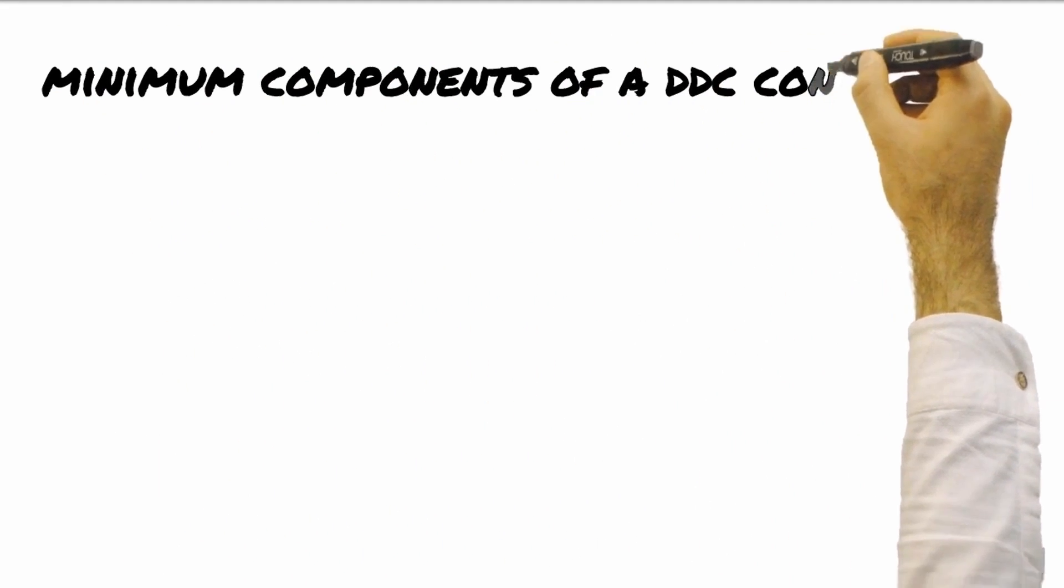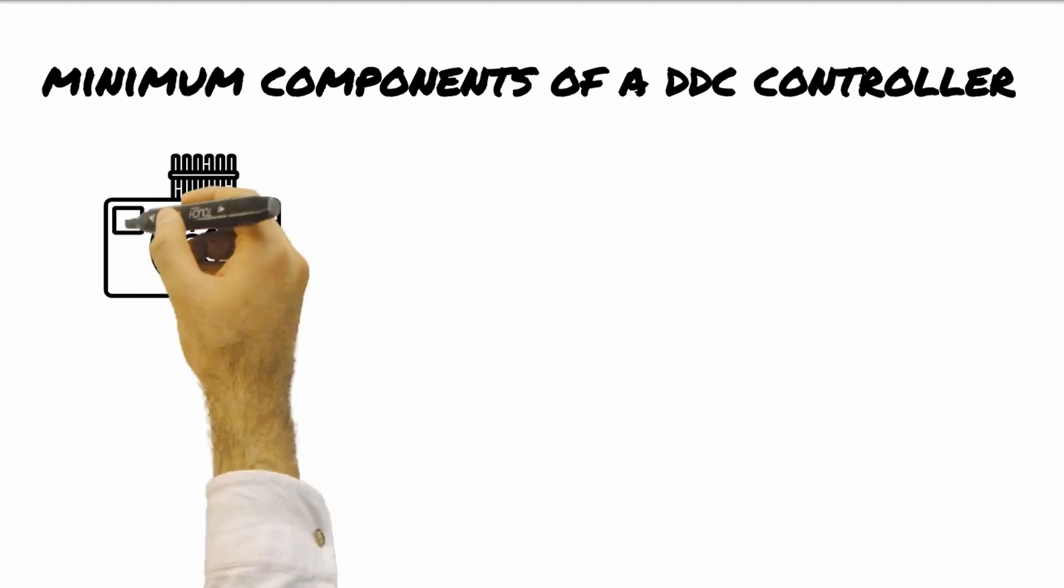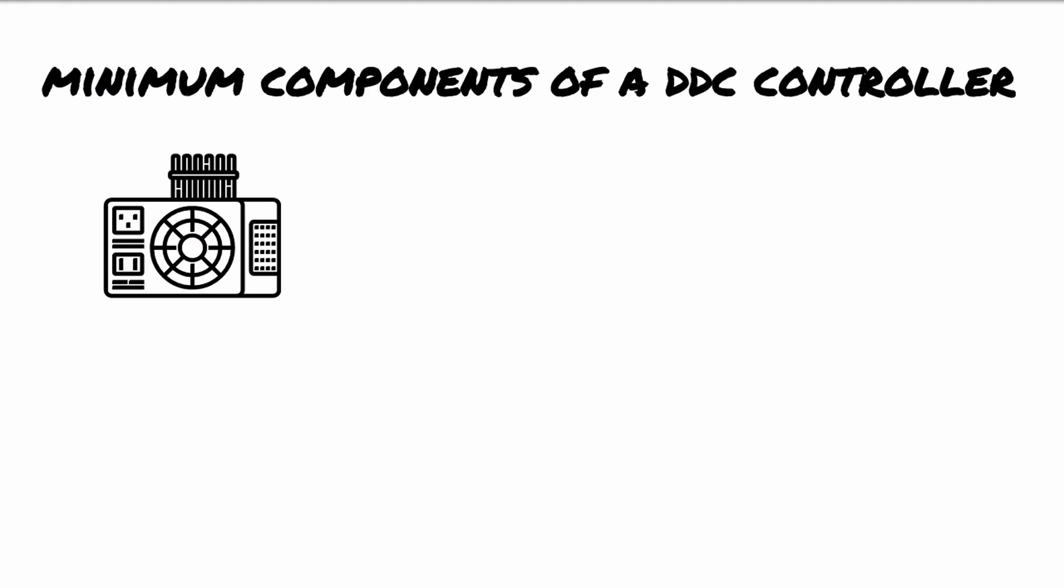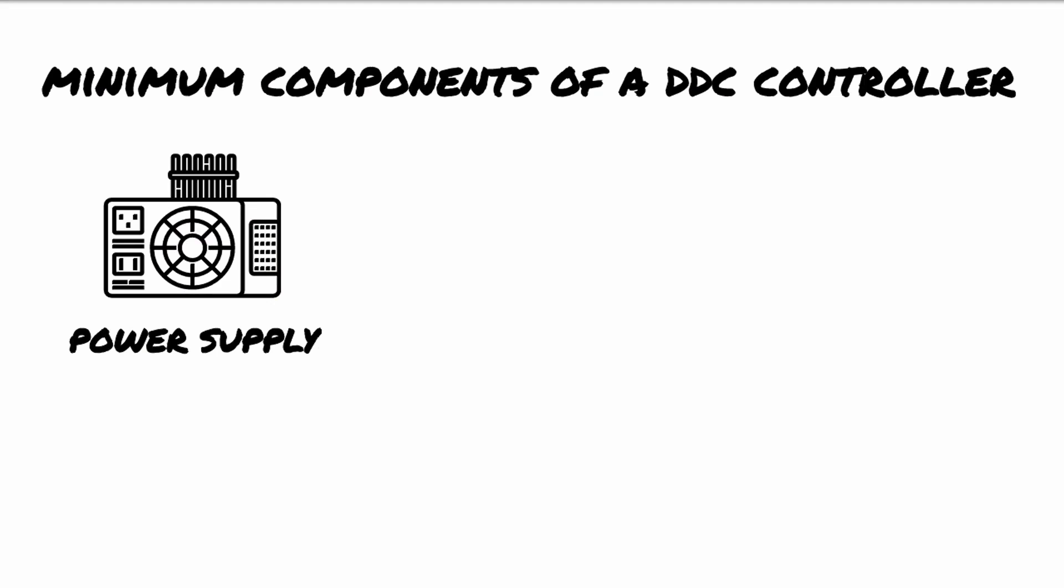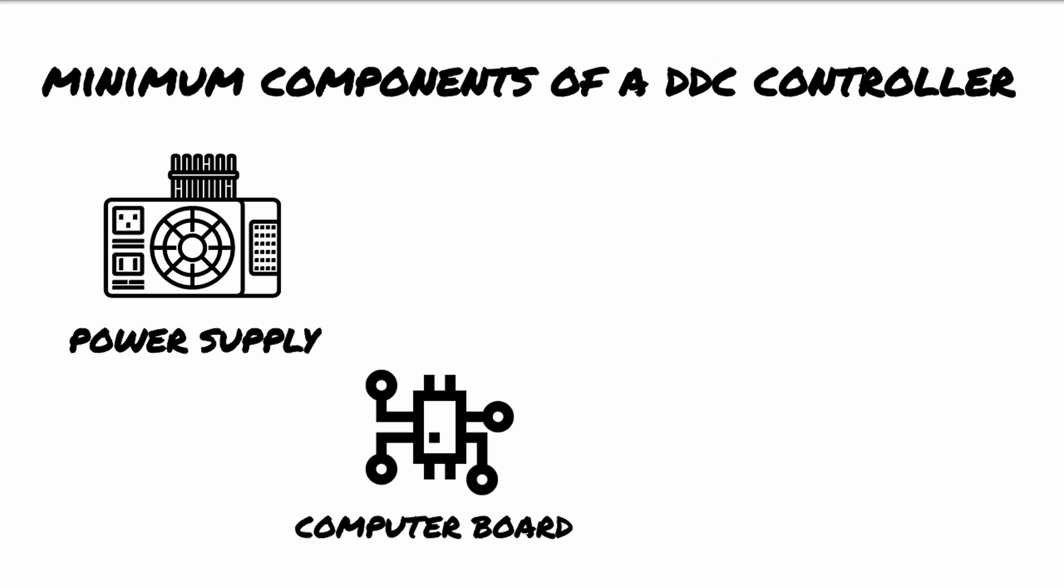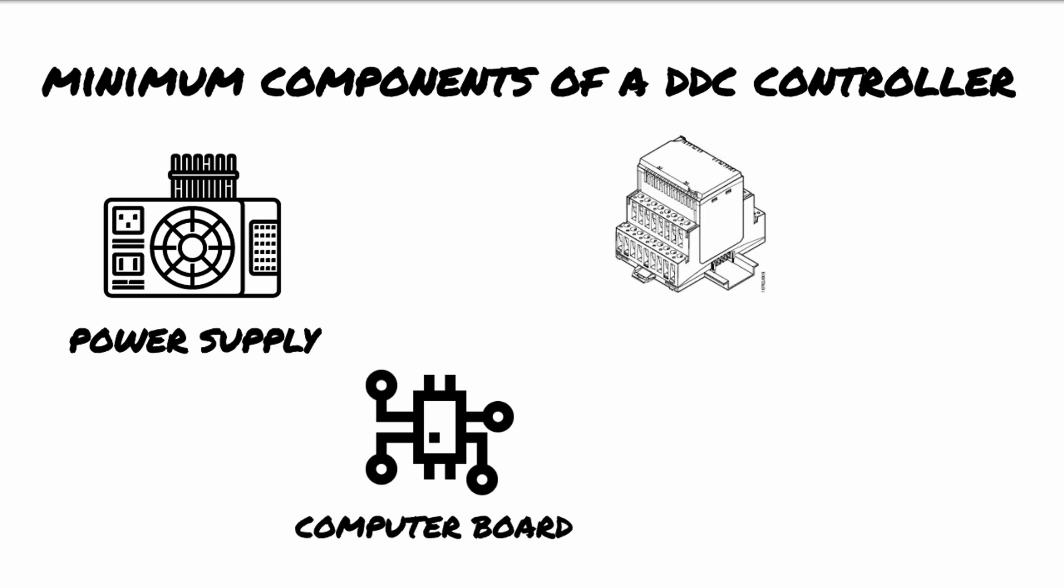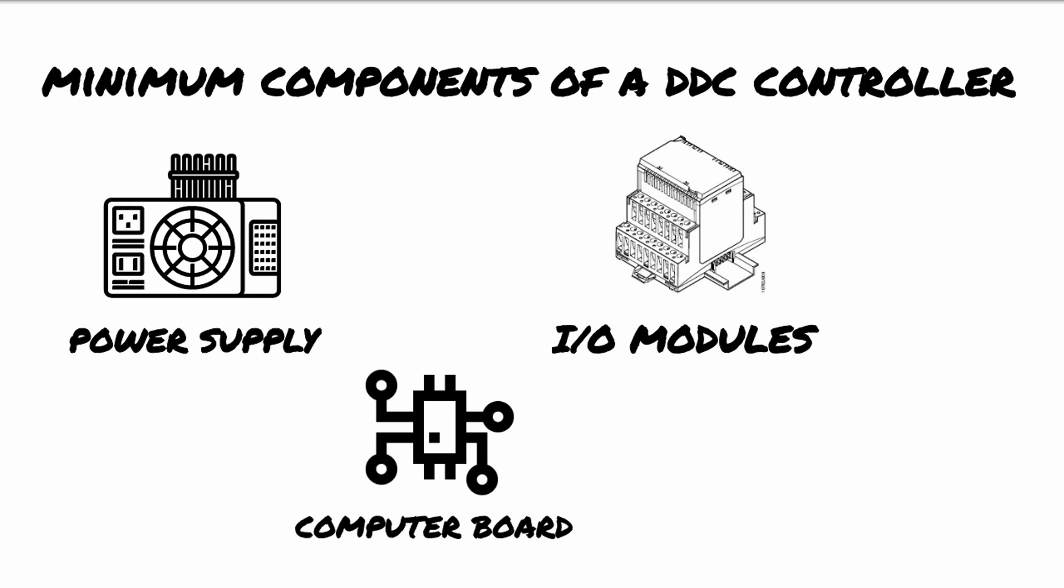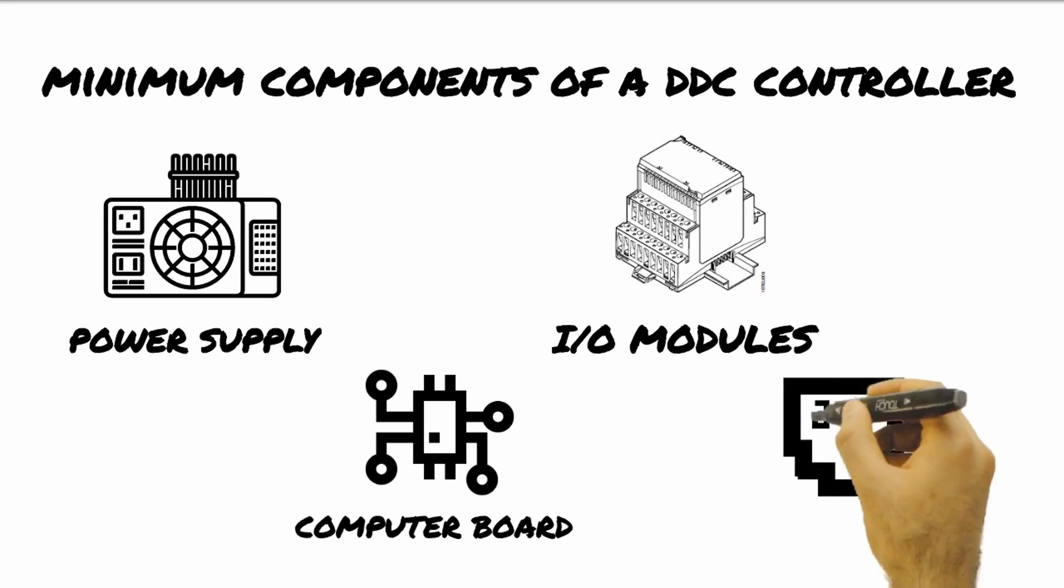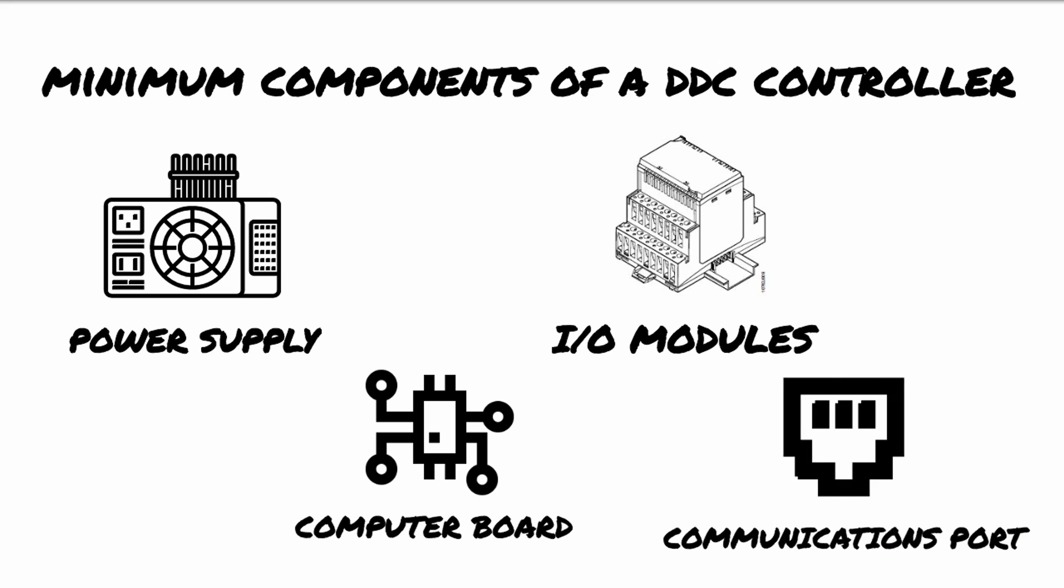The minimum components of a DDC controller are the following. First is the power supply which powers the computer board at a low DC voltage and the I/O points with DC and 24 volts AC. Next is the computer board to run the control software. And then we have the I/O modules with screw connections for wires in and out, analog to digital and digital to analog conversion hardware. And we also need the communication port to enable the computer board to have the software loaded and updated when required.